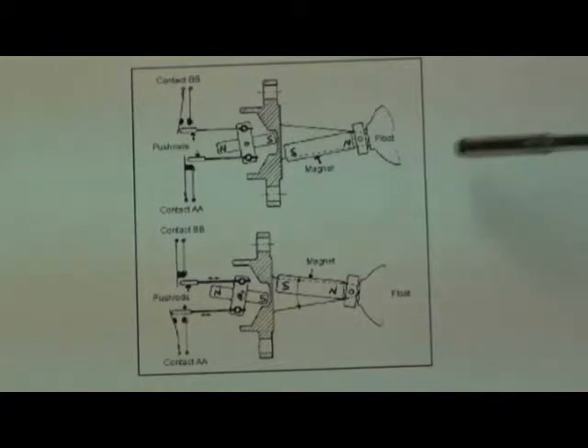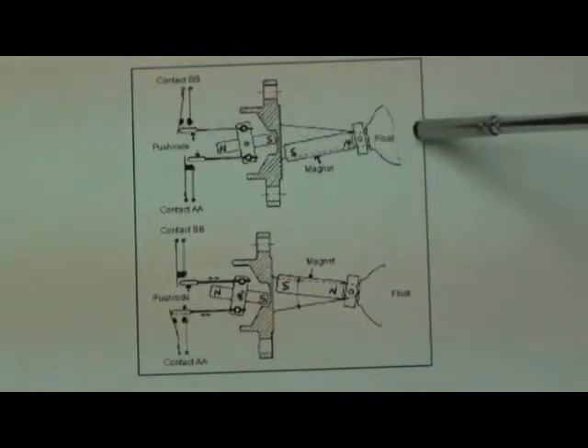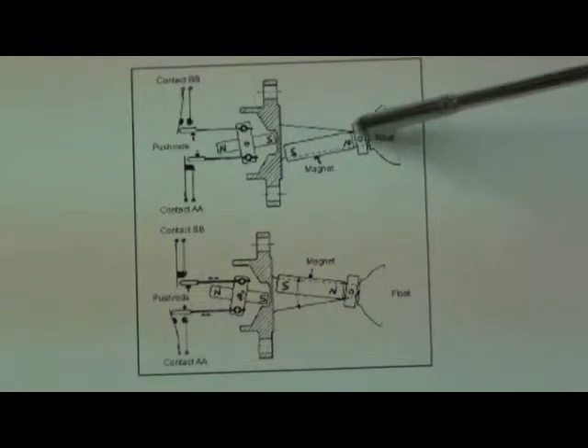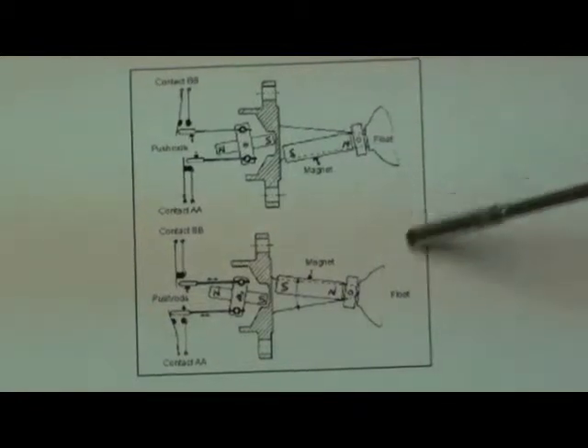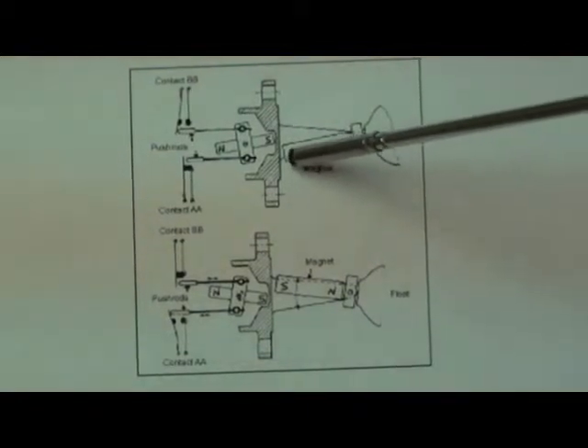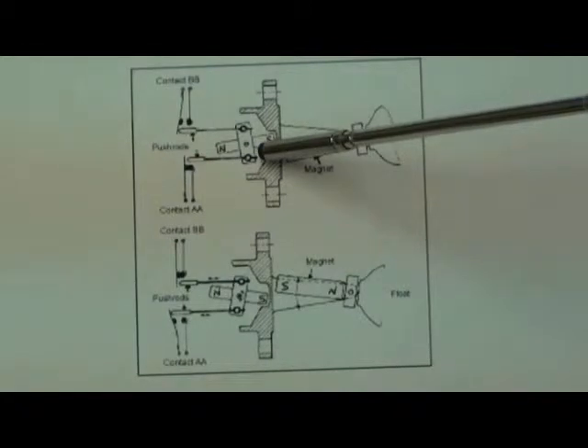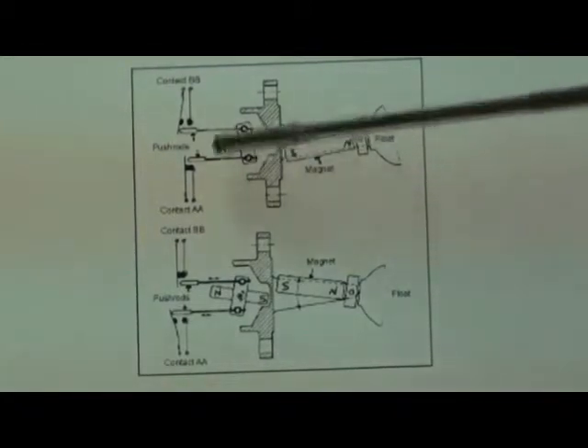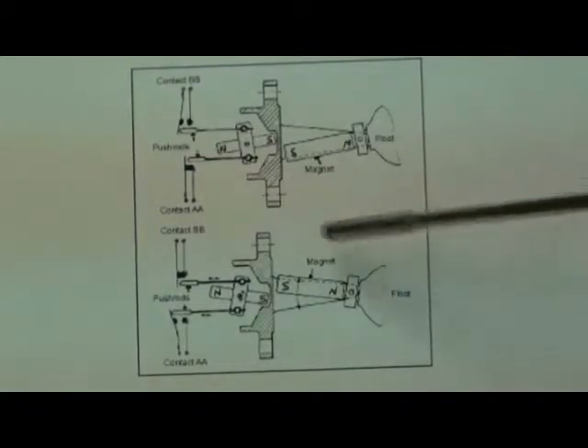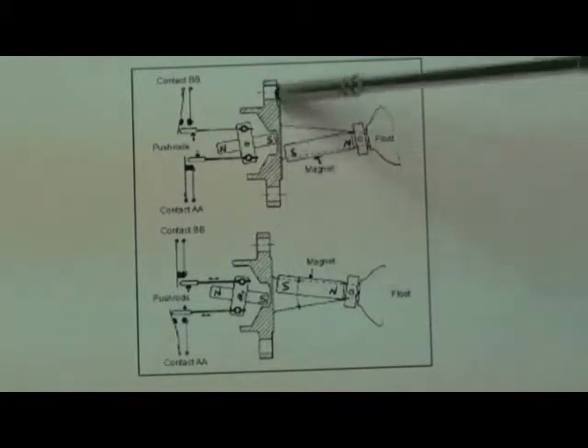Consequently, a change in liquid level - here you can see the float in the high level position. As that falls, this magnetic pole will face directly the same pole in the switch head mechanism through a non-magnetic diaphragm here.